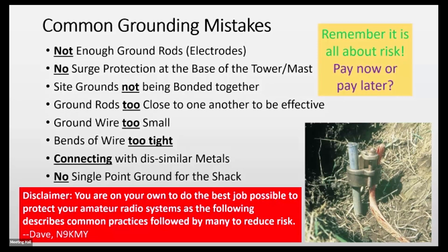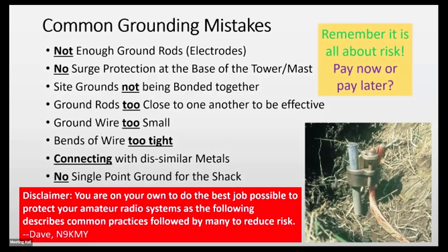What he did was put in a great inductor, and the lightning never went past that point — so guess where the lightning went? Into the building, into the controller. I contacted the manufacturer, sent them a picture of that lightning system, and he said they'd effectively nulled and voided their lightning protection, because breaking a rule on the installation does that. So they contacted the site, straightened the bends back out, and never had any problem afterward that I heard of.